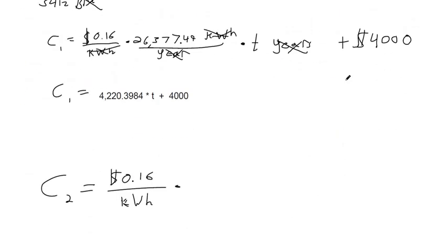Right? So every kilowatt hour you get from the power company with this heat pump, you are dividing that kilowatt hour by 3.5 because your system has a coefficient that's bigger than 1. Sorry, for every 1 kilowatt hour you get from the electric company, you get 3.5 kilowatt hours of heat.